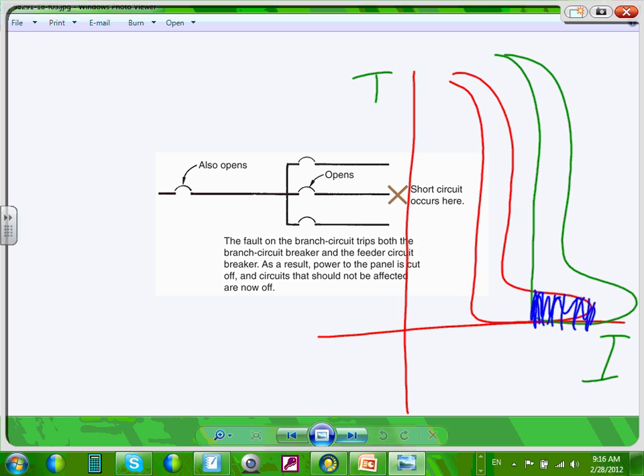Let's just say this was a 20 amp and this was a 100 amp. So this will be the 100 amp, and this will be the 20 amp. Cool? Can you guys see that if they're coordinated, they're not touching each other. Are they touching each other anywhere except at the bottom? Suppose we have a short circuit right here, and this short circuit was 4,000 amp. At 4,000 amp, let's say we're going to trip in half a second, 0.5 of a second. Because they are touching each other, both of them will trip at this value.